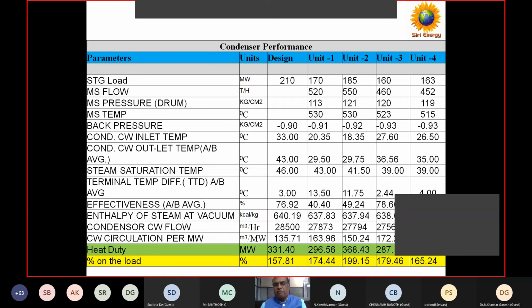So that way we have to see where all the optimization potential is there. We told them you can improve the impeller efficiency and also the casing efficiency by some coating—coatings are now available that can give maybe 3 to 4%. We asked them to do it for one pump, and when tested practically we showed there was a 5% saving in that one pump. Based on that, they took up other pumps for the same improvement.